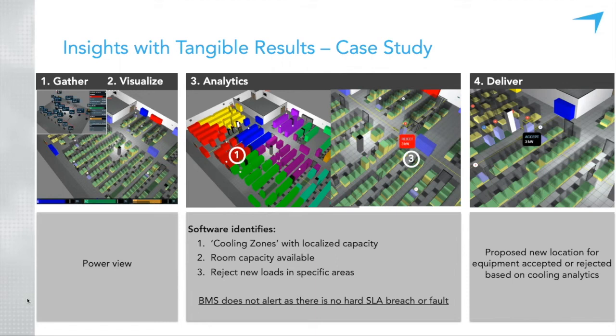This is a very important feature. We're also able to use the same kind of analytics almost in reverse, to fail or simulate the failure of an air handling unit, and then recalculate the zone of influence to see how that impacts in terms of resilience.